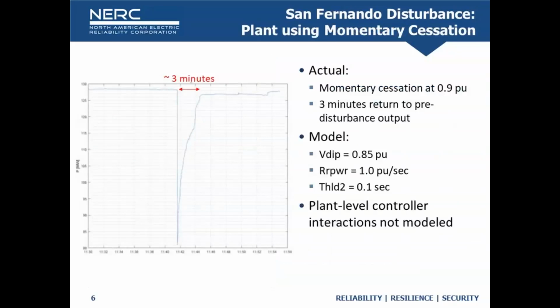So this is an example of a plant that went into momentary cessation in this event. They reported back to us saying, yes, we use momentary cessation. It occurs at 0.9 per unit. For those that are new in this community, momentary cessation is where the resource ceases current injection to the grid, both active and reactive current, and pauses, then comes back over a period of time, which is specified in the inverter controls. So this facility is using 0.9 per unit as its threshold.